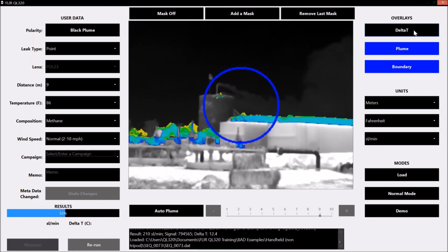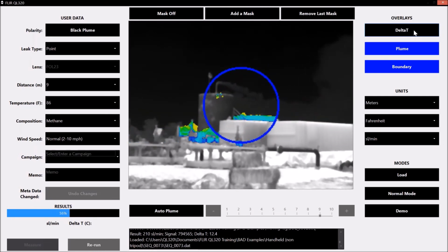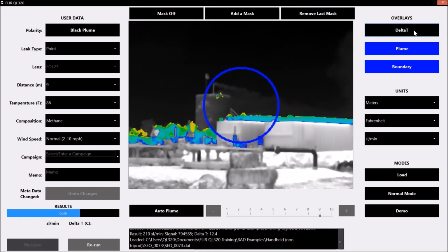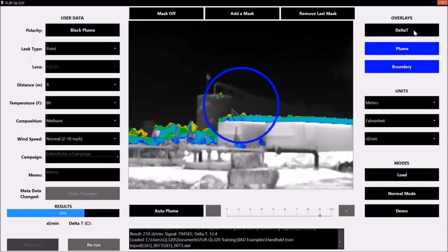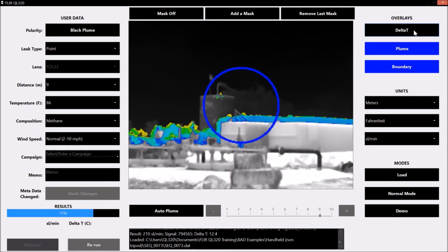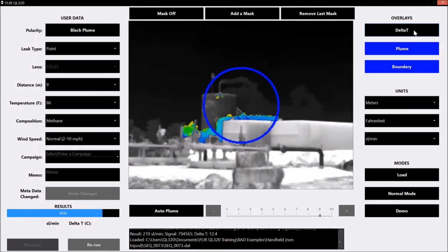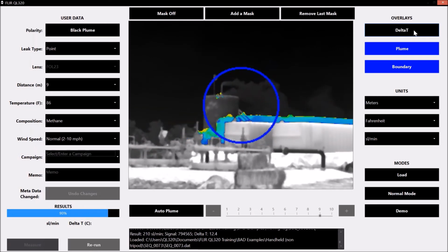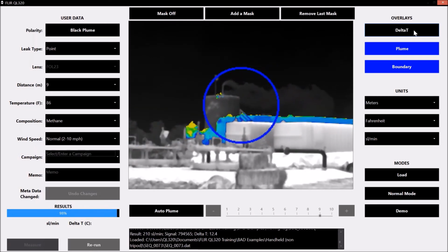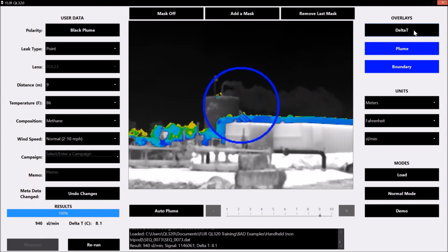The camera sees that as a dramatic change. So you can easily look at this and say, wow, this is really an evident leak. The other issue with this is an evident point release, and ideally you would want that to be as close to the center of the screen as possible. But even the smallest amount of movement, if you think that you're holding it super steady because you've got strong hands, it's really, really challenging to do that with the way the technology is developed today.